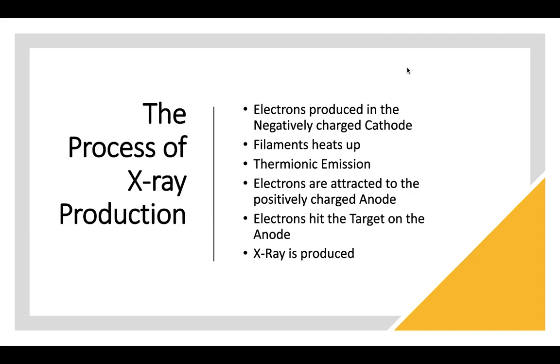The process of X-ray production first happens with electrical current passing from the cathode to the anode. After the filament is heated up, electrons will bounce off the filament and create a space charge. This is due to thermionic emission. Electrons join the electron stream, then start to flow to the anode side of the X-ray tube.